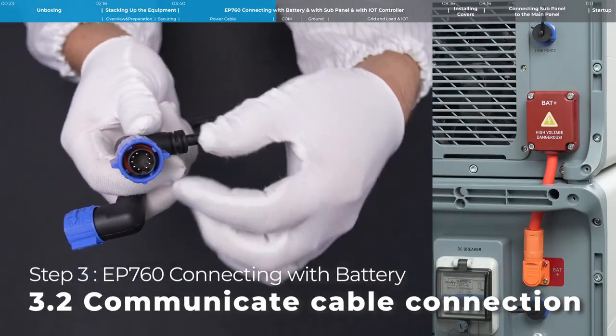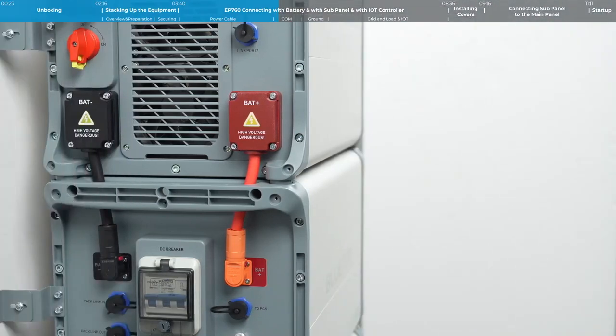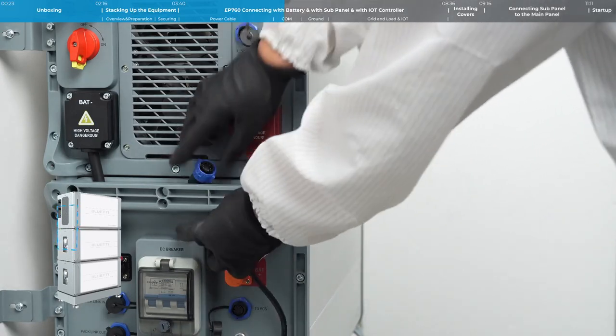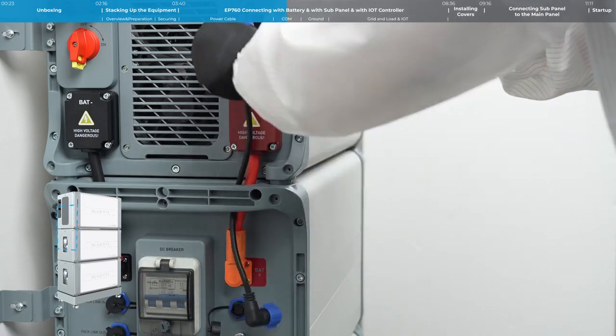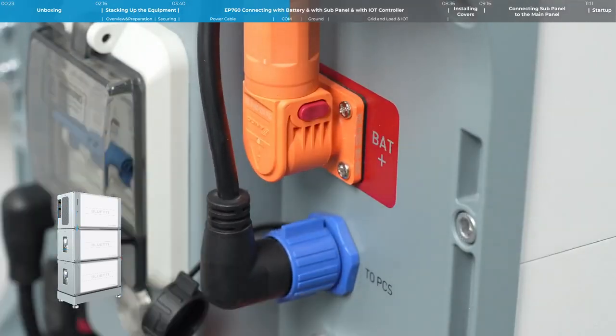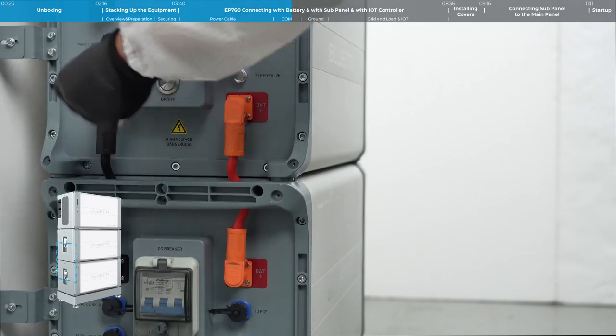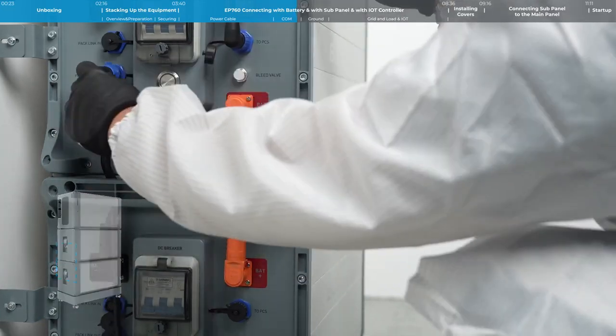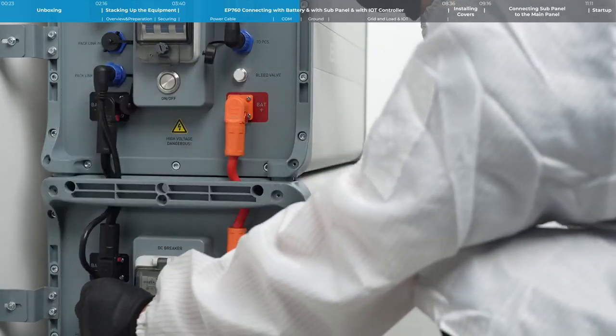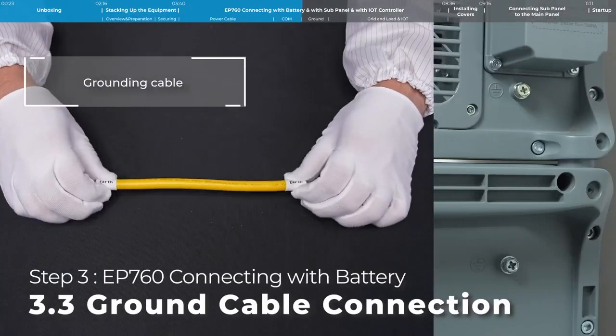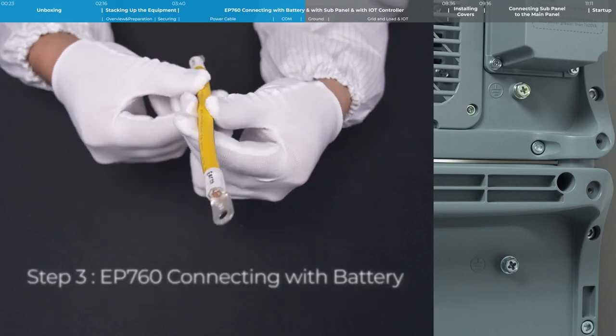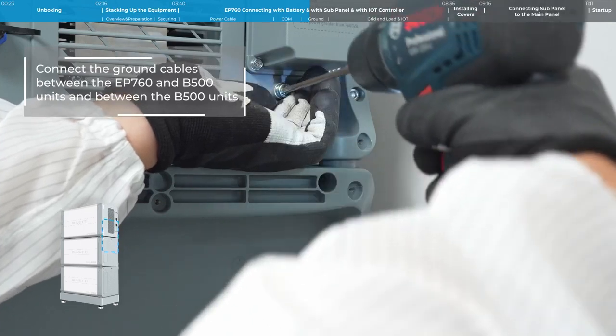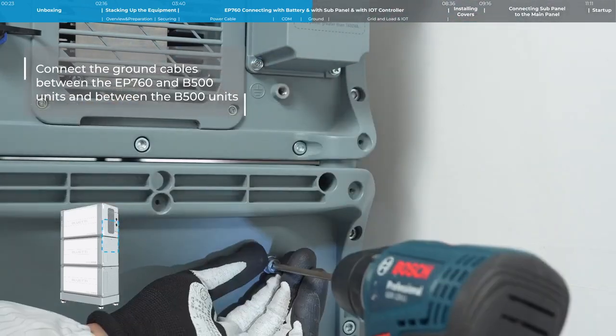Both ends of the communication cable have a quick release structure. Connect the communication cable. The ground wire is a yellow-green copper wire. Connect the ground wires between the EP760 and B500 units and between the B500 units.